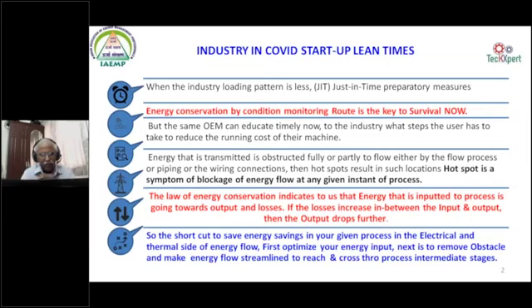The second one is removing the obstacles in the energy flow and streamlining the energy flow. Let us say the case of compressed air, the streamlined flow of compressed air at around 7 bar is around 8 to 10 meter per second. So whenever turbulence is peeping in, whenever the streamlined process is getting disturbed, this is where we have to see why the turbulence happened and how this can be corrected. By correcting this, automatically the energy conservation will come and the energy savings will come.